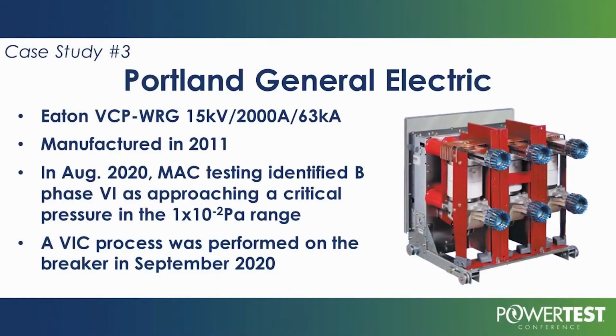This was manufactured in 2011. This was a generator breaker. It was a very important breaker, a very expensive breaker. The interrupter, $15,000, $20,000 for an additional pole assembly for this breaker. When you measured the ion currents of the 3 poles, the ion current was much higher on B than A and C. Even with all the insulators removed, with everything clean, with no outside factors, only current passing through the interrupter, the B phase was much higher than A and C.